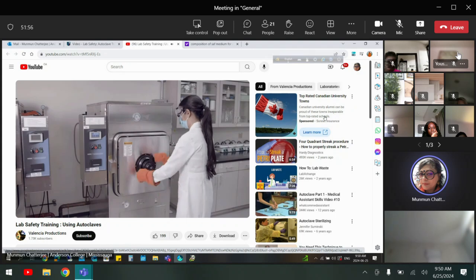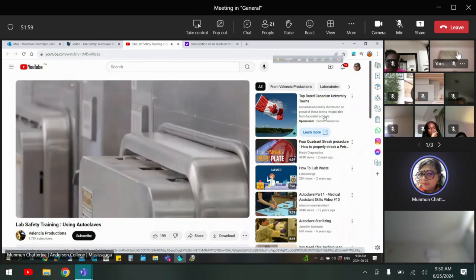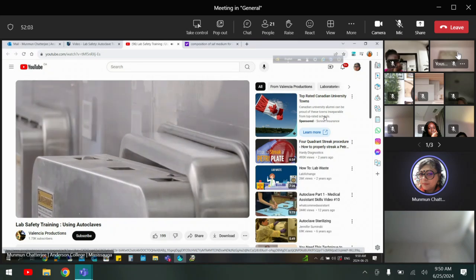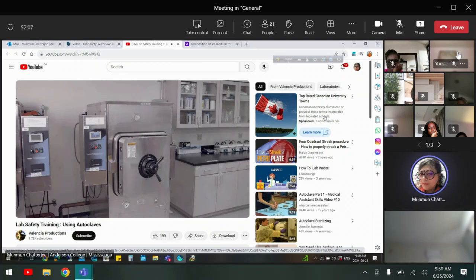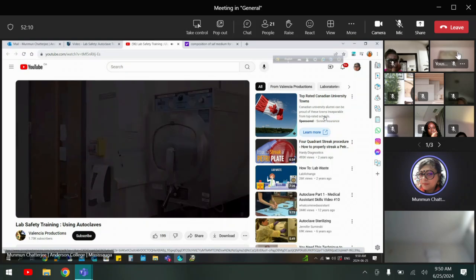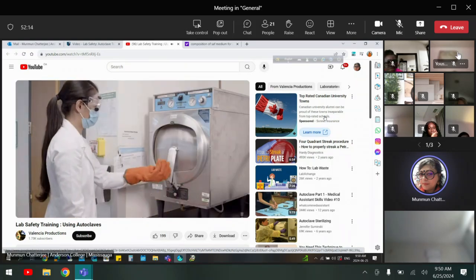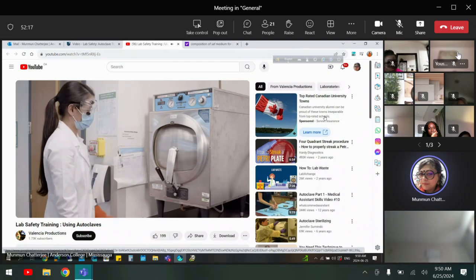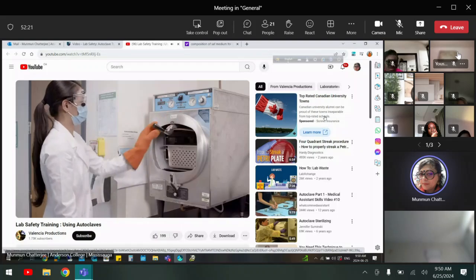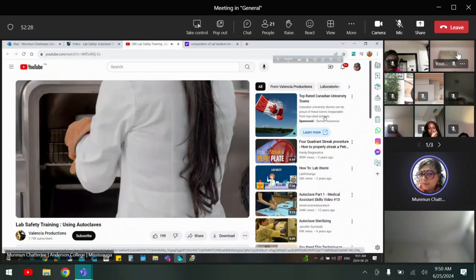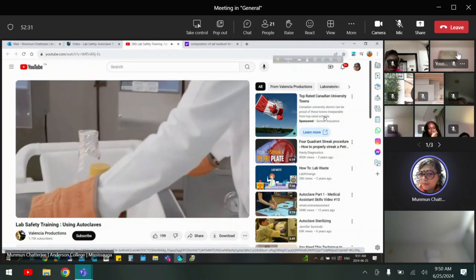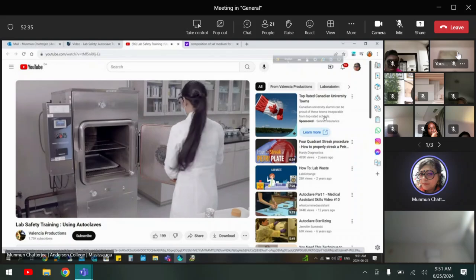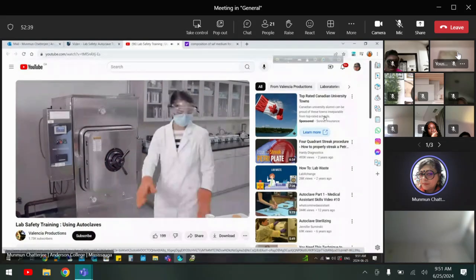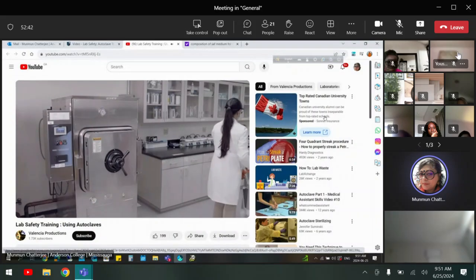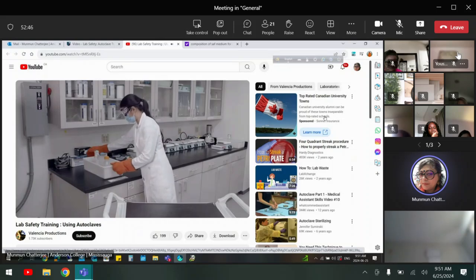If your autoclave door swings open, stand behind the door and carefully open the door no more than 1 inch. This will release residual steam and allow pressure within liquids and containers to normalize. Allow the autoclaved load to stand for 10 minutes in the chamber. For other models, where the door opens outward and upward, step to the side and release the handle. After the initial burst of steam is released, push the handle up. Similarly, allow the autoclave load to stand for 10 minutes in the chamber. After the load has cooled for 10 minutes, cautiously remove the items as they will still be hot. Do not agitate liquids, as this may lead to boil over, which can cause burning or scalding. Leave the door of the autoclave slightly ajar. Resealing it will shorten the lifespan of the rubber gaskets on the door. Place items in a safe area to cool.